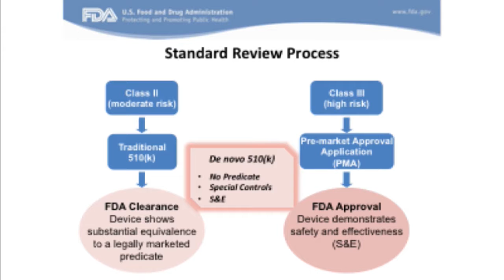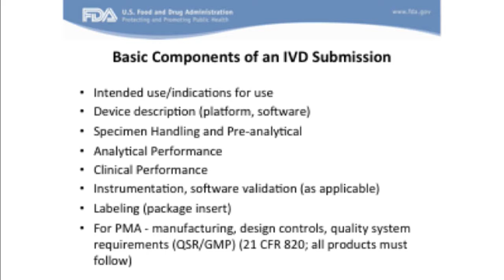So the basic components of an IVD submission include, most critically, the intended use. This would include the analyte, the instrument, the interpretation, the use. The device description, any specimen handling or pre-analytical requirements, analytical performance, clinical performance, instrumentation, software as applicable, labeling, and for PMA or high-risk products, we do review in the pre-market setting manufacturing, design controls, and quality systems. These things are required for all products, but pre-market review is only needed for high-risk products. So what does FDA review? We review the sample collection, the instrument or assay, the analyte extraction, and the software or interpretive aids that are used in the device.